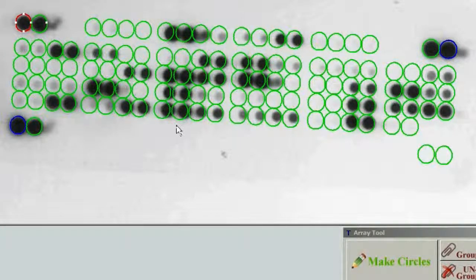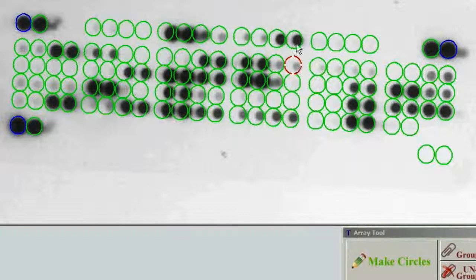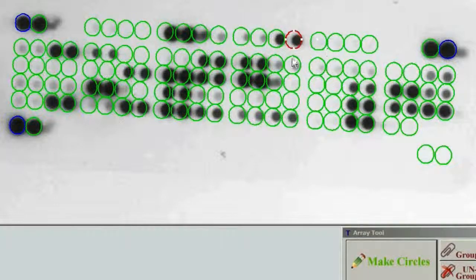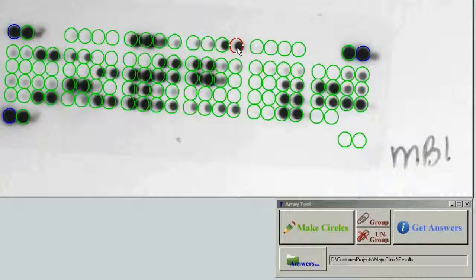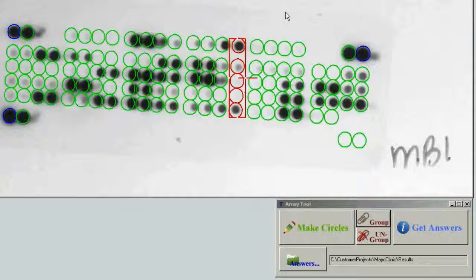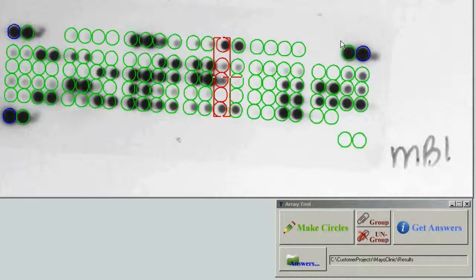In a perfect world, the circles for the template would overlay exactly with the dots from our results, but because the kits are not perfect, they don't always line up. You can right-click over any ROI or circle to activate it, then use the arrow keys to better align the template with your actual results. At any time you can click Make Circles again to reset to the original calibrated location. You can also select a group of circles, move them together with arrow keys, then ungroup and proceed to the next group — a faster way to align circles with the dots.